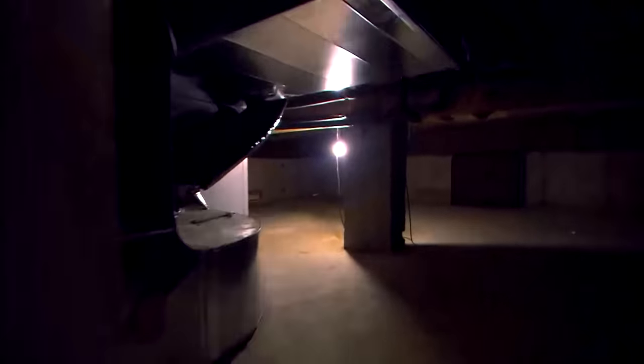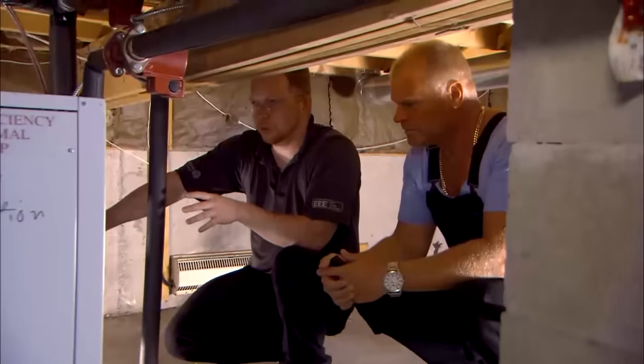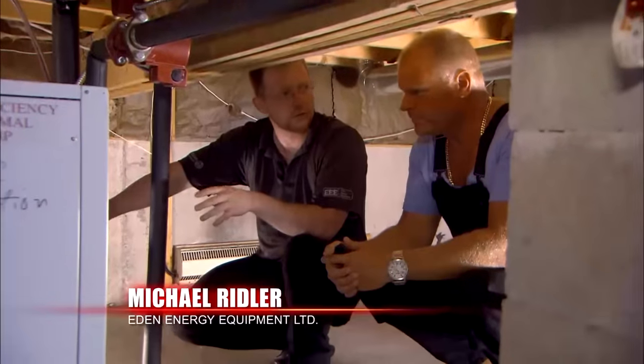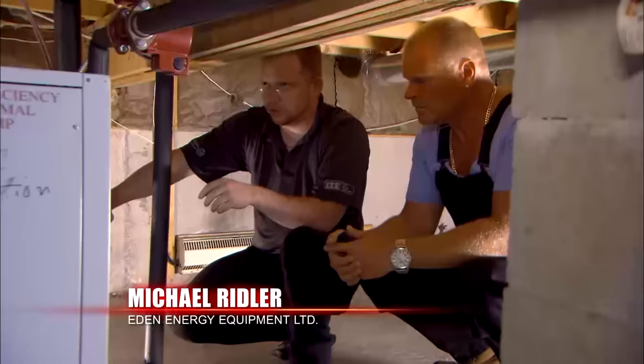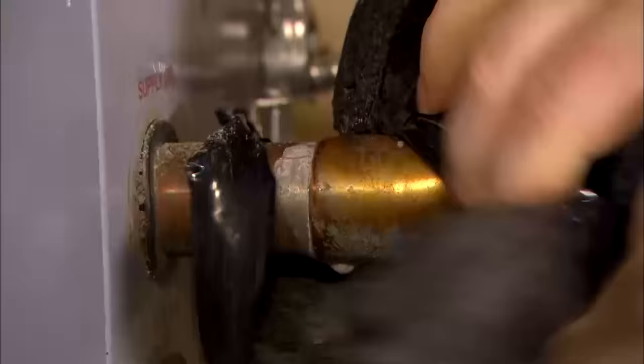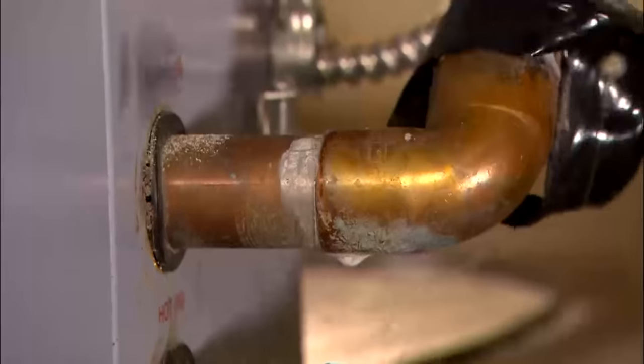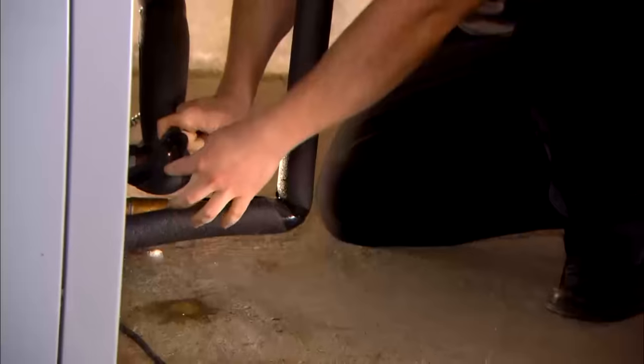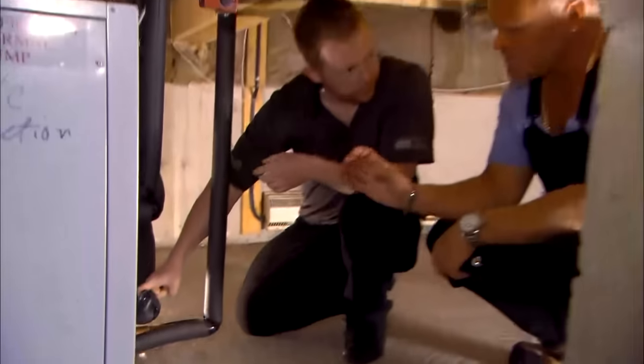Geothermal systems, the way you really benchmark the piece of equipment is based on what's going on in the actual loop itself. So what we need to do is take a pressure temperature reading right here on the equipment. What you would typically find is a Pete's port, a pressure temperature gauge that sits on this connection, and it tells us the temperature.